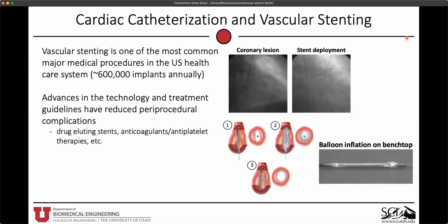Now, coming from a mechanics background, the deployment of a stent, I consider is really a mechanical solution to a clinical problem. And I say that because we talk about the inflation of a stent. These balloon inflation pressures are incredibly high, thousands of millimeters of mercury. You have an incredibly non-homogeneous deformation of both the stent and the vessel that's shown by that balloon inflation video there. And of course, you have permanent deformation of this stiff device to leave it in place.